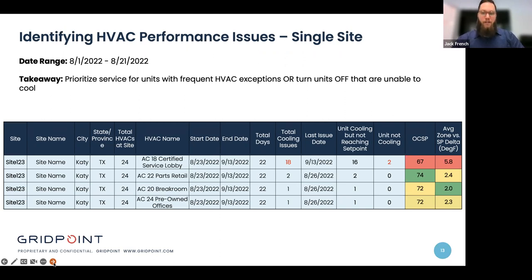Now, we talked about best practices earlier. So there's an occupied cooling set point for this unit at 67 degrees. That is outside of what we would recommend for best practice. And then finally, the column on the far right is average zone versus set point delta. So this is how far the zone temperature was from its configured set point. On average, let's just round up and say 6 degrees. So if our occupied cooling set point is 67 and we're actually averaging 73, maybe we should consider raising the set point to somewhere around 73 so we give that unit a chance to have some relief. If it's not going to consistently meet 67, we've got to return to best practices and say, what is the data telling me? We're not giving this unit a chance to breathe. This is going to cause premature failure of the unit.